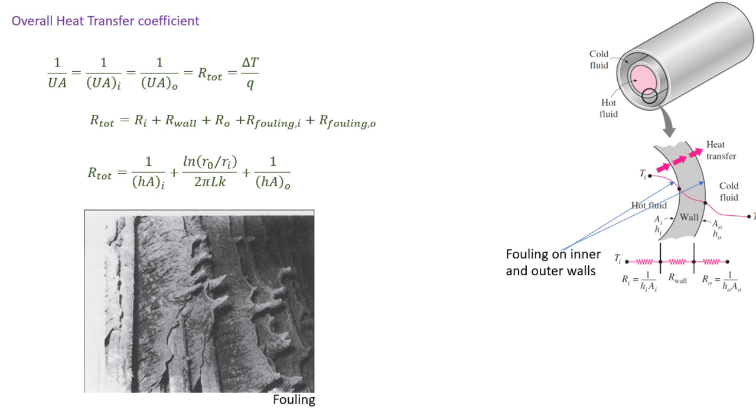They often happen because of precipitation deposits like calcium from the fluid, but they may also happen due to corrosion or biological growth. We often express those fouling factors for a surface area and the units will be meters squared Kelvin per watt.